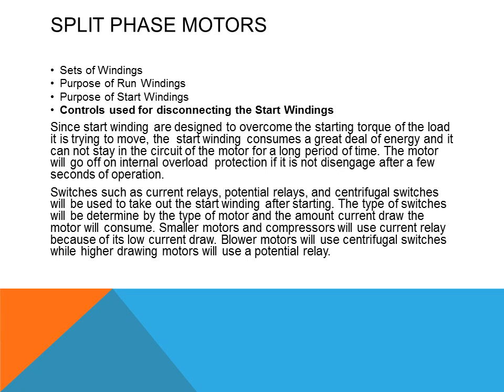Since the start windings are designed to overcome the starting torque of the load, they consume a great deal of energy and cannot stay in the circuit for a long period of time. The motor will trip on internal overload protection if the start windings are not de-energized or disengaged after a few seconds. Switches such as current relays, potential relays, and centrifugal switches are used to take out the start windings after starting. The type of switch is determined by the type of motor and the amount of current draw. Small motors and compressors use current relays; blower motors use centrifugal switches; higher current-draw motors use potential relays.